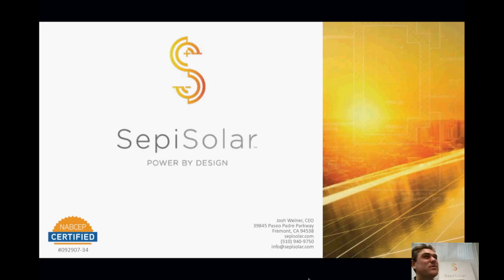The 120% rule is this really cool code that was almost like the enabler for solar. Back in the day, if you wanted to plug solar into a service panel, most panels are rated for the max size of the service disconnect that feeds them. So you might have a 100 amp panel with a 100 amp breaker in a residential system, or a commercial system with a 3,000 amp service panel and a 3,000 amp main service disconnect. Without the 120% rule, you couldn't add any solar to that because it's already maxed out.